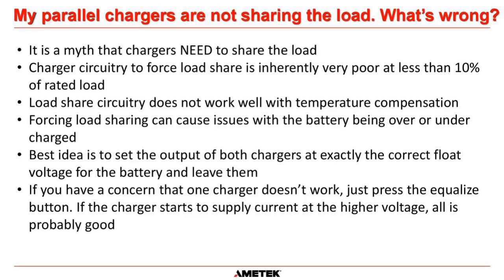It's a myth that chargers need to share a load. Forced load share circuitry is very poor at less than 10%, especially less than 5% rated load. Load share circuitry does not work with temperature compensation. So if you have temperature compensation on your system, one battery could be at a different temperature than the other battery, and therefore it's telling the other charger to increase or decrease its voltage accordingly, which messes with load share. Forced load share can cause issues with batteries being over or undercharged. And I've given you the best idea: set both chargers at exactly the correct float voltage for the battery and leave them. Okay, that's the best thing to do.